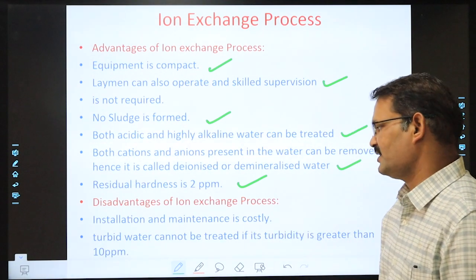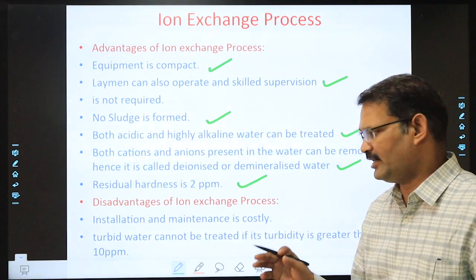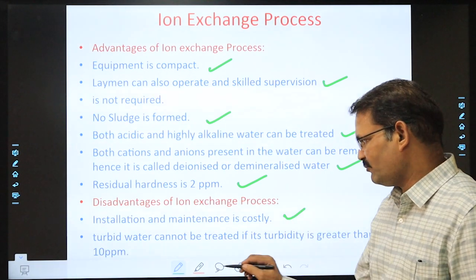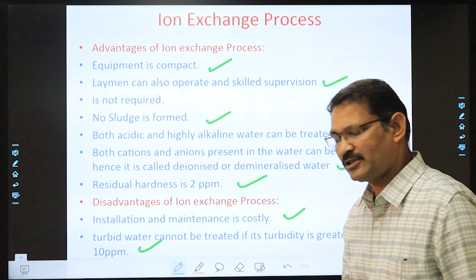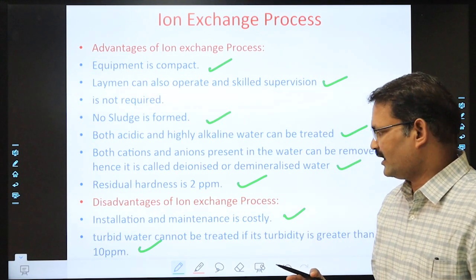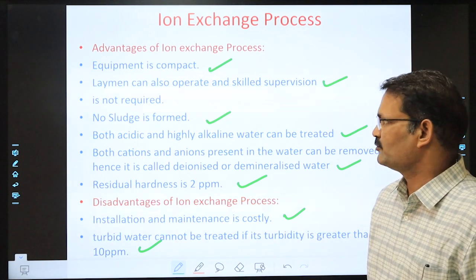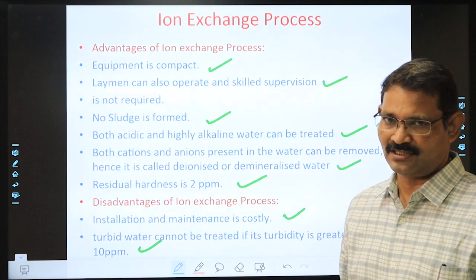The disadvantages are that installation and maintenance are very costly, and if the water is highly turbid, with turbidity of more than 10 ppm, we cannot treat it using this ion exchange process.